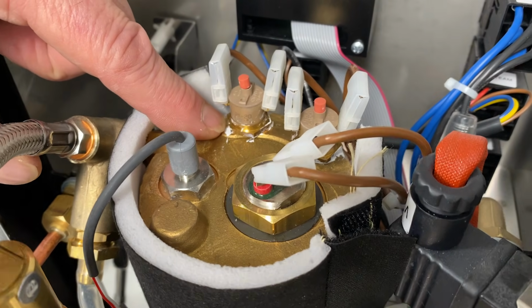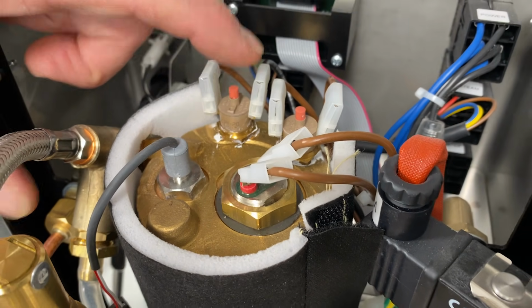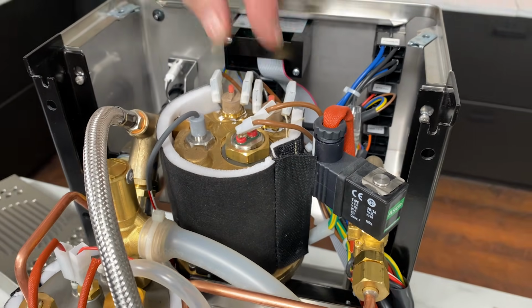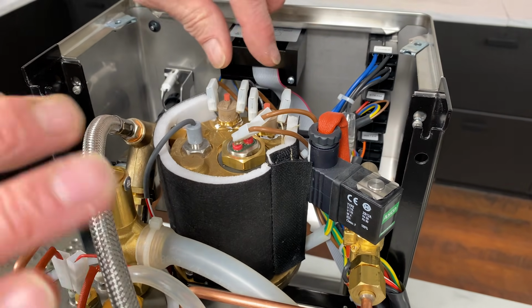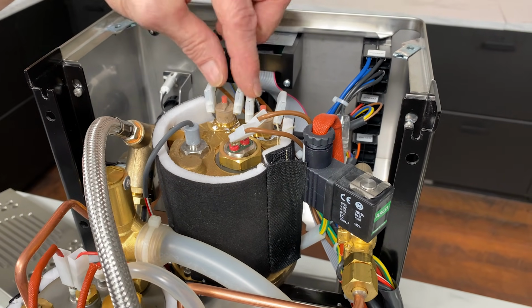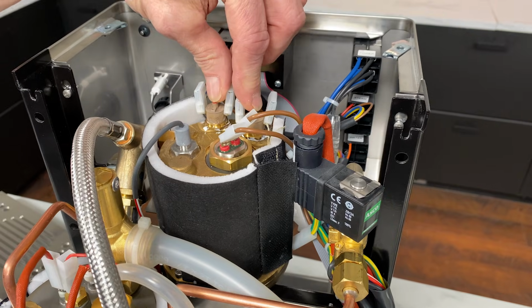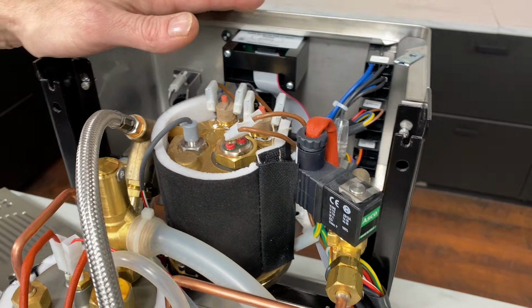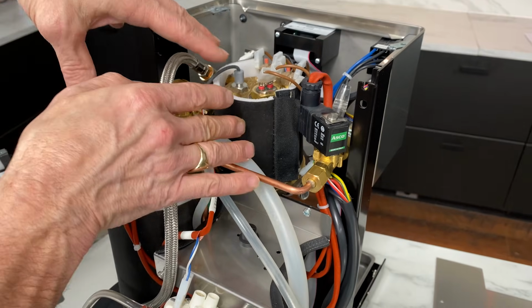That's like a heat paste. It helps the heat transfer so it can sense it. If they get above 140 degrees, these will pop like circuit breakers. And then if you had to reset them, you just take the screws off the top, get in there and push those back down just like you would a circuit breaker. So that is the brew boiler.